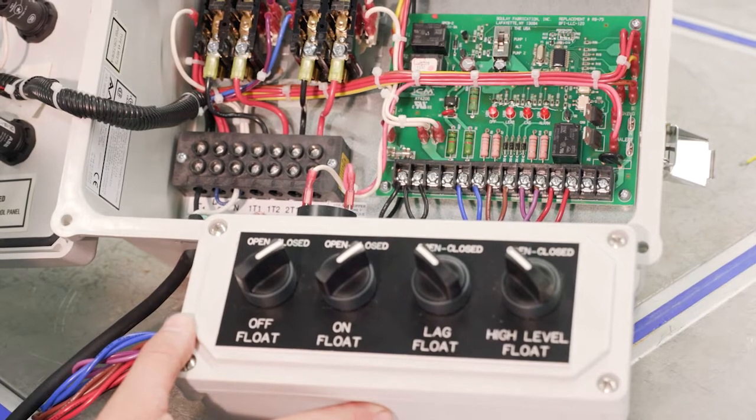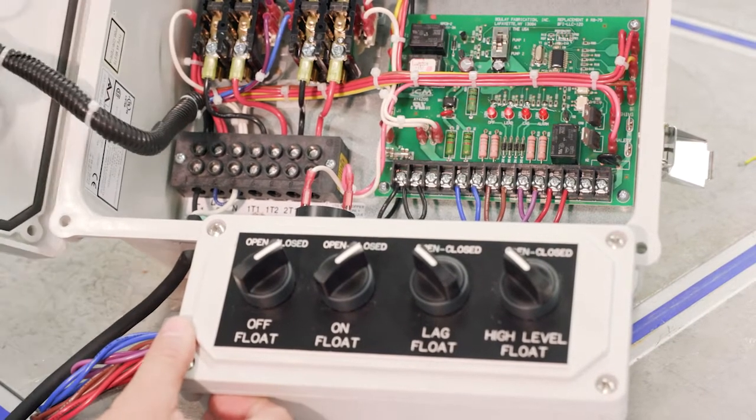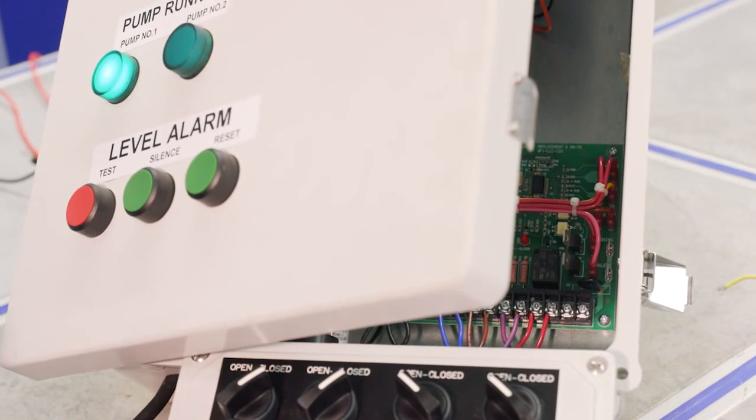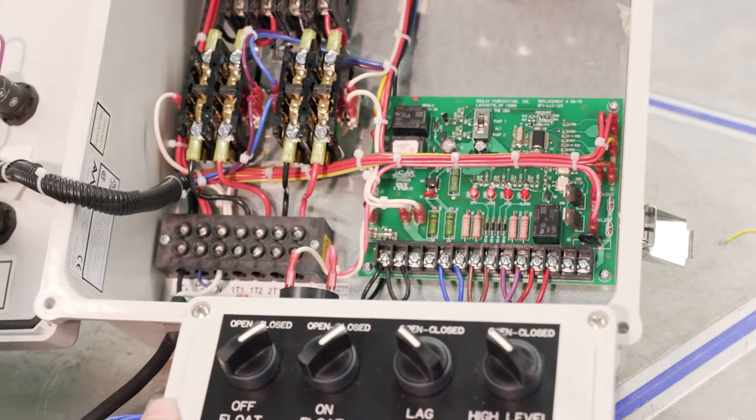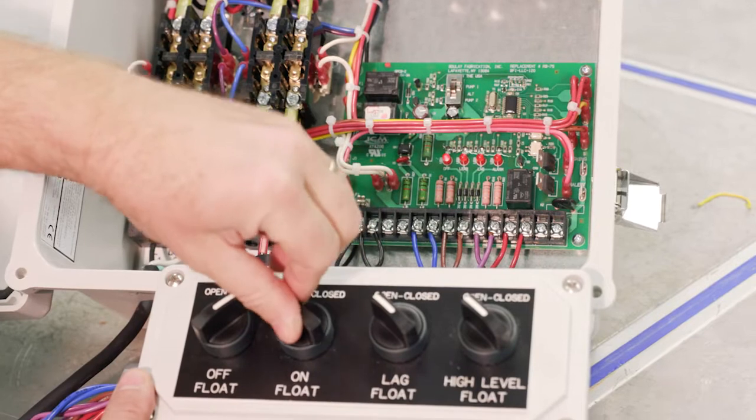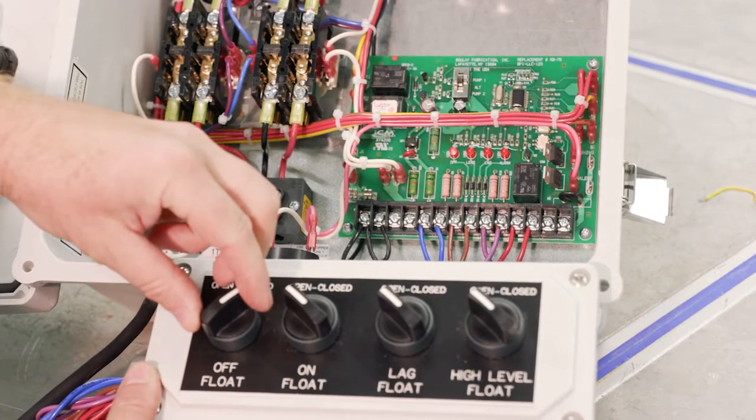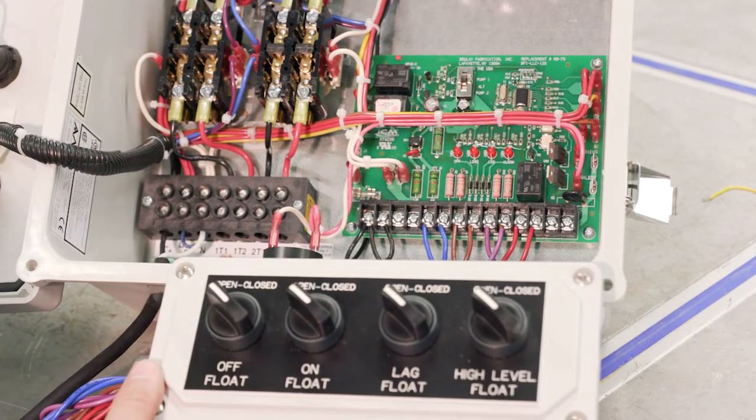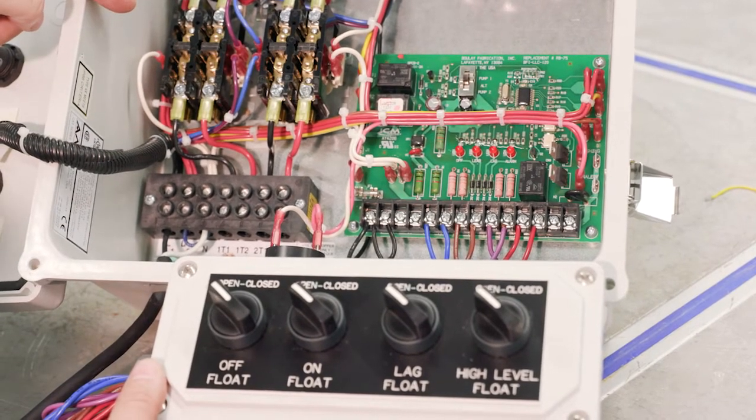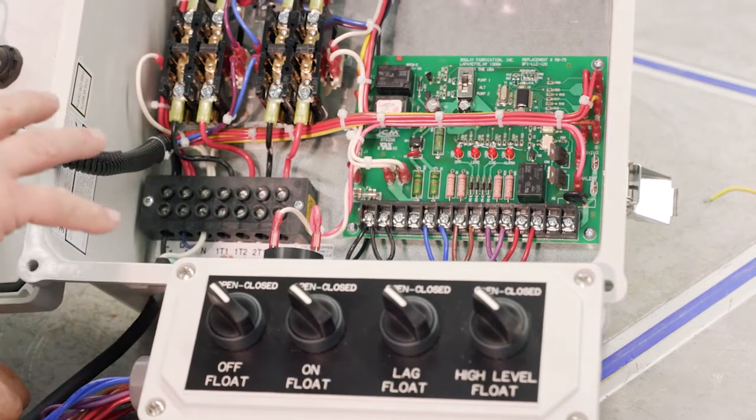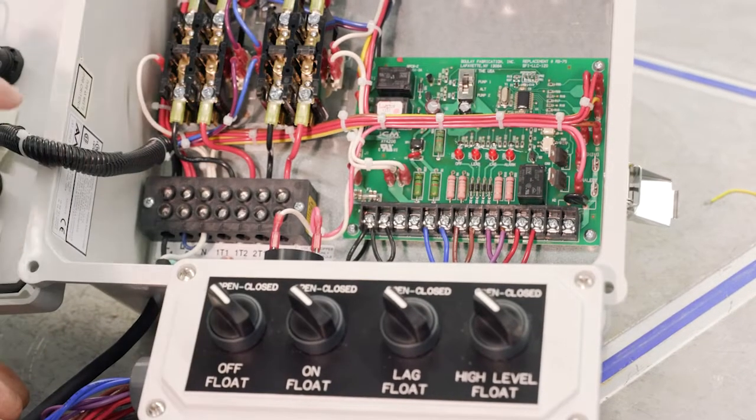Pump one is now running. Does its job, on float opens up, then the off float, and then it turns it off after a delay. So far, so good with our alternation, our LEDs, our pump running.